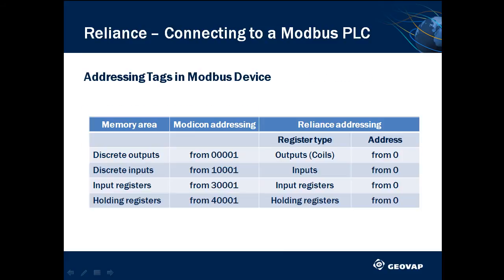In the Reliance system, the address of a tag defined within a Modbus device consists of a register type and an address. While memory areas of a different type in a Modicon device are addressed using an offset, tags in the Reliance system are addressed from 0 for each register type. For example, holding register 400001 in Modicon is equal to holding register 0 in Reliance.